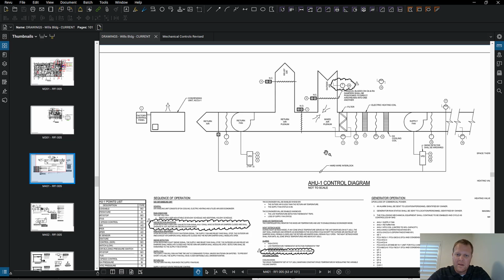So you need to know the systems and subsystems. Let's, for instance, talk about air handler unit 1. Can you just give me, mechanical contractor, a breakdown of what subsystems you need online before you can go do a full checkout of the air handler? So what subsystems would they need online? Well, he needs power, he needs VFDs, he needs power to the condensing unit, he needs power to this. And he's going to start listing all this power stuff.